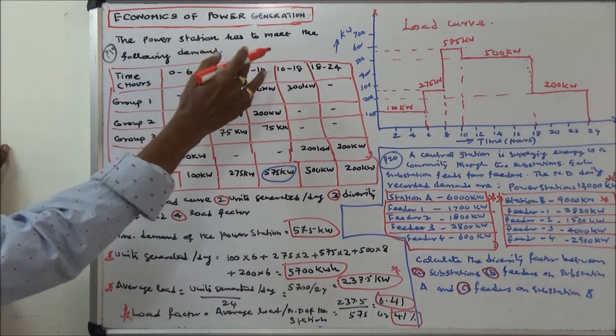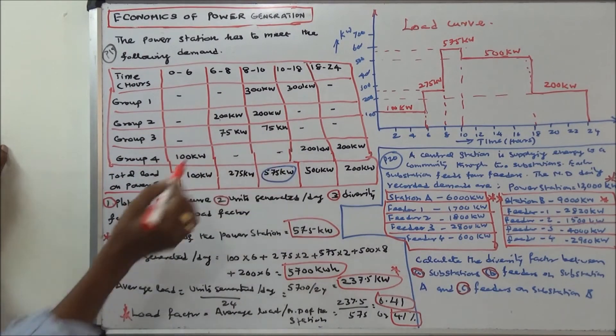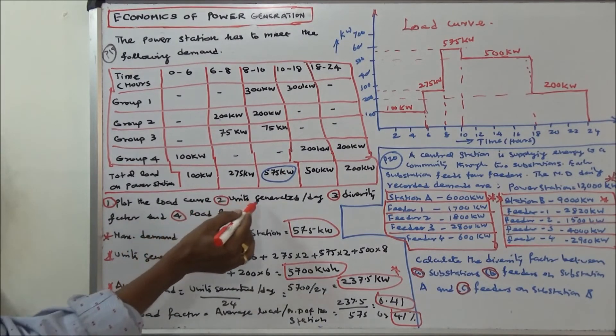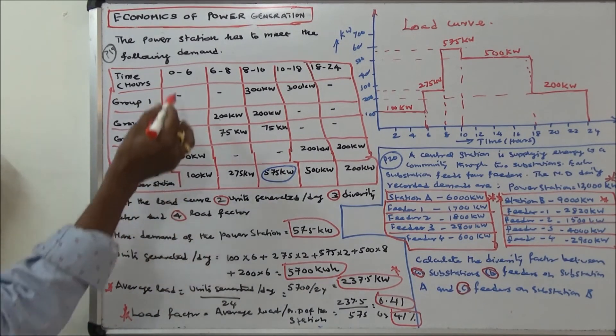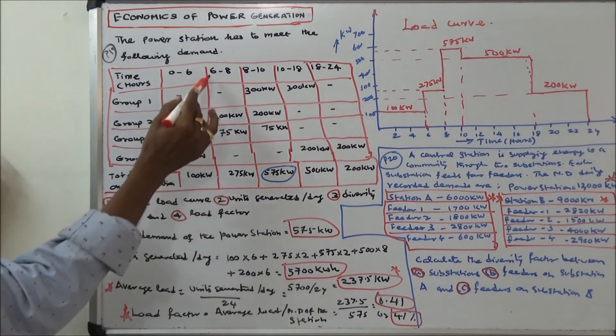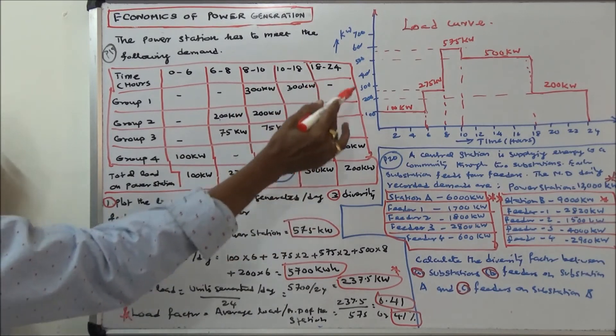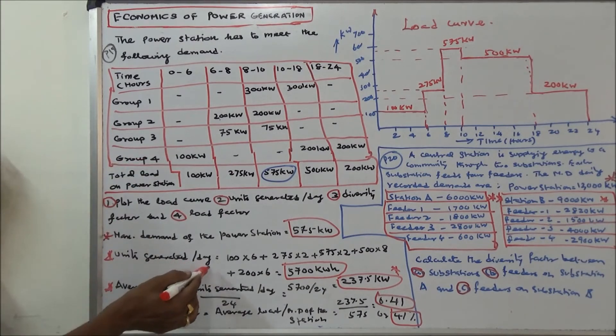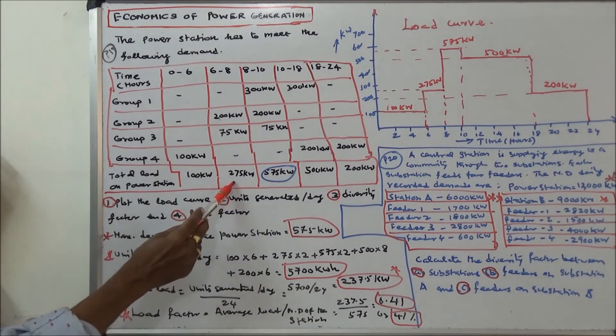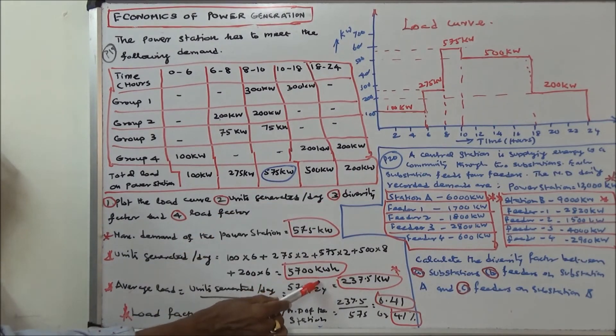Third problem: a power station meets demands for four groups. Total loads: 0–6 hours = 100 kW, 6–8 hours = 275 kW, 8–10 hours = 575 kW, 10–18 hours = 500 kW, 18–24 hours = 200 kW. Maximum demand of the power station is 575 kW. Units generated per day: 100×6 + 275×2 + 575×2 + 500×8 + 200×6 = 5700 kWh.